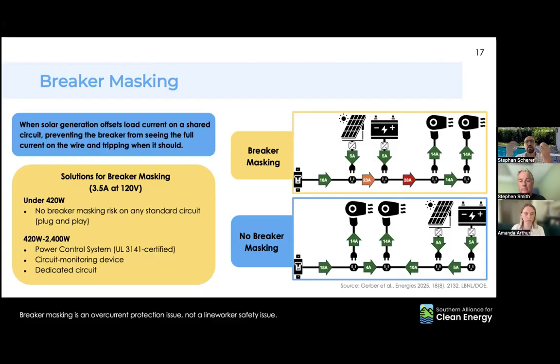Breaker masking is essentially the breaker only knowing how much is going in. It doesn't know if you're pushing power from the other side and overloading a wire between two outlets, as we're showing here. So there's another standard, UL 3141, that says you have to install something like a power meter, which measures that circuit specifically. Then there's a simple calculation: the sum of your usage plus the sum of your solar production can't go over that limit. That's the simple part of it.